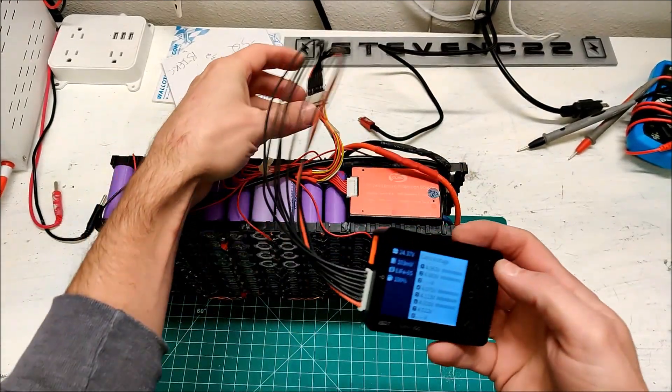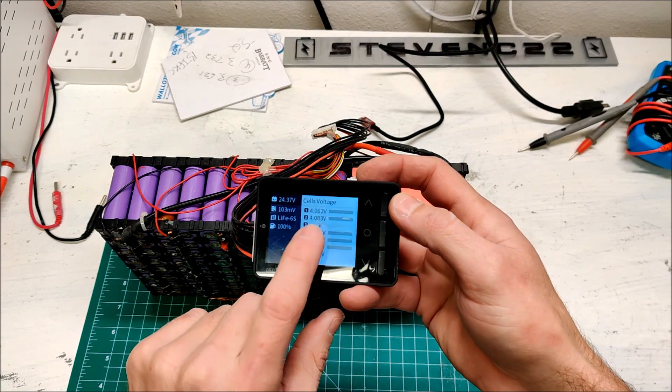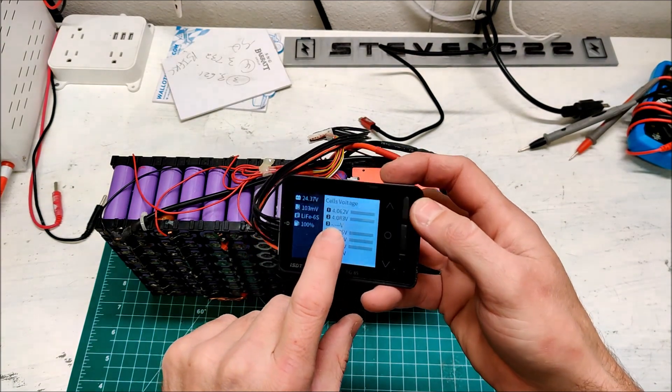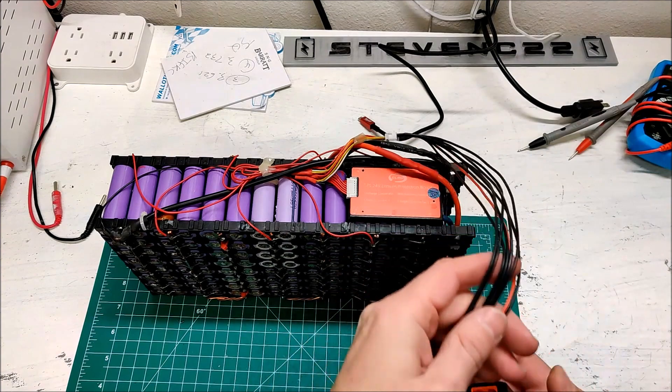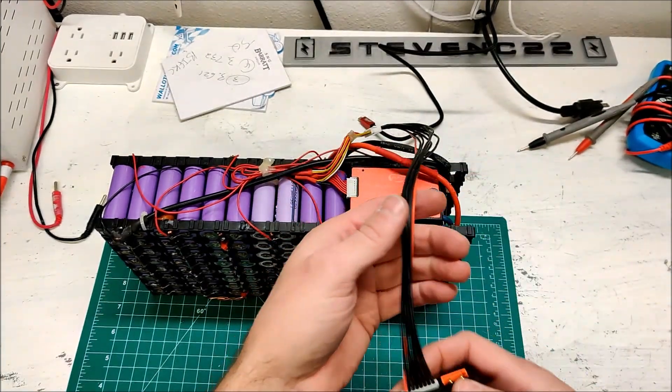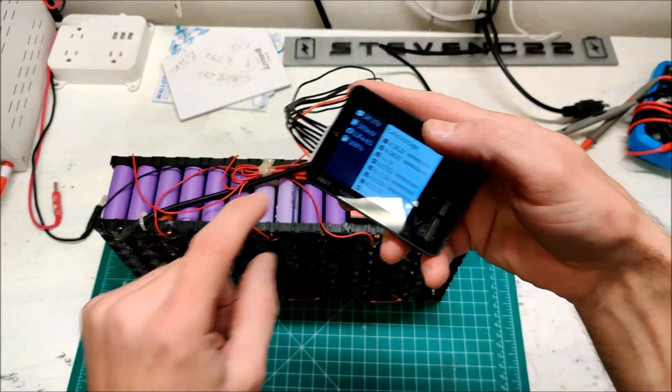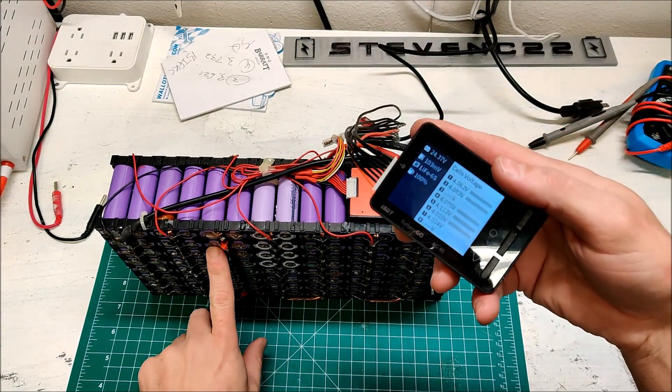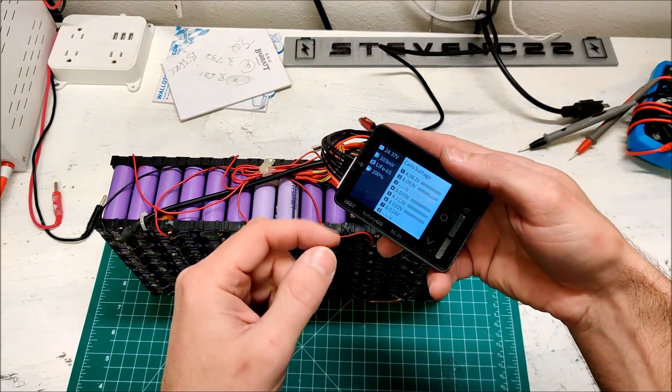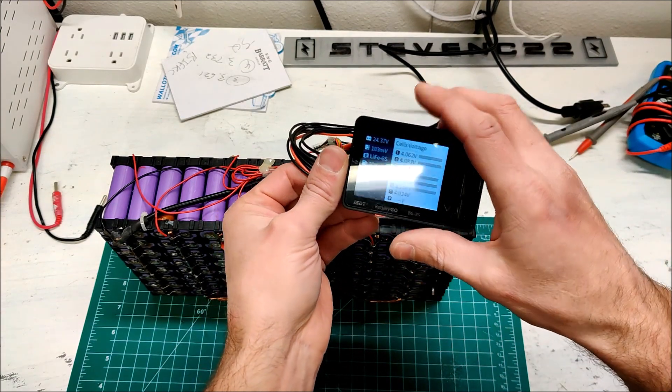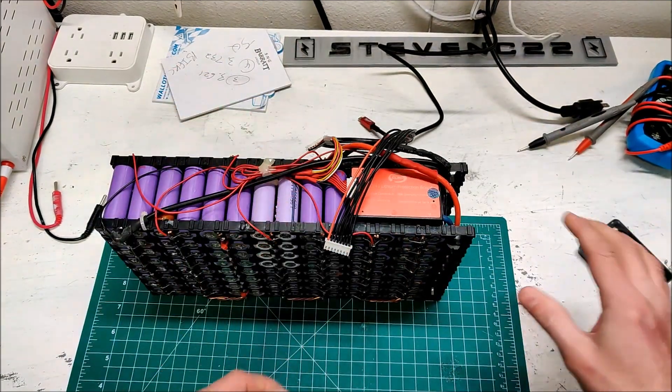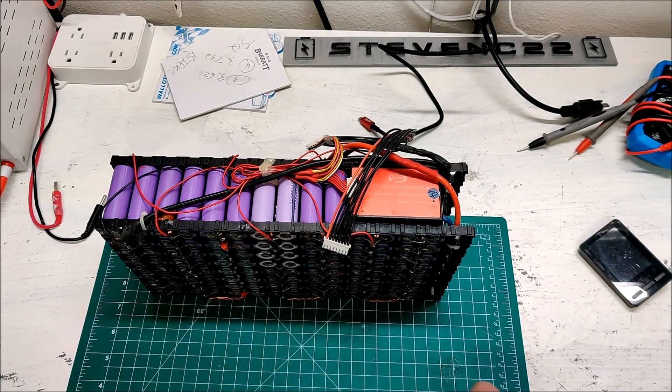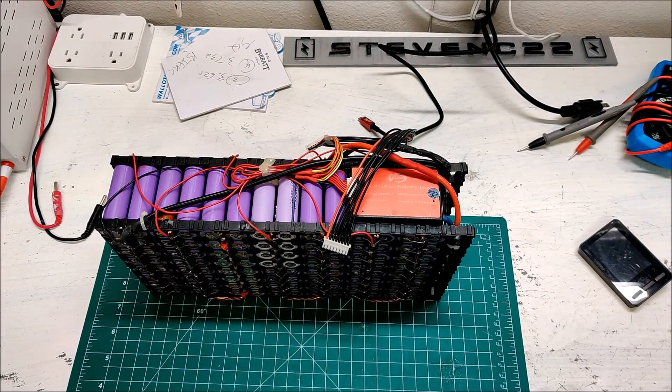Well it was turned off because pack 3, the voltage was below 3 volts on pack 3 while everything else was at 4 volts. It's turned off now because I actually cut the fuse wires on pack 3 checking cells. I was doing some troubleshooting, so that's why pack 3 is currently turned off, but pack 3 itself discharged and there are some bad cells in pack 3 here.